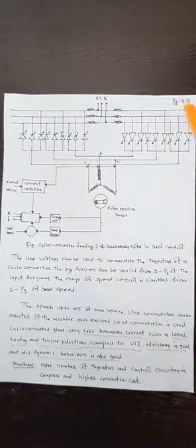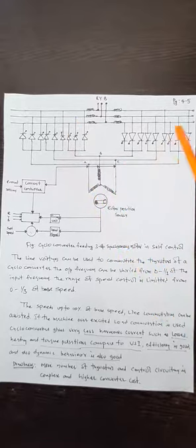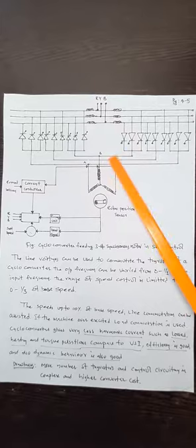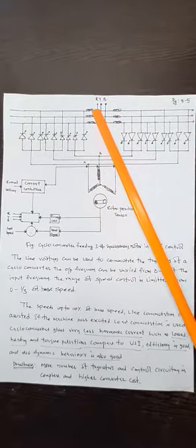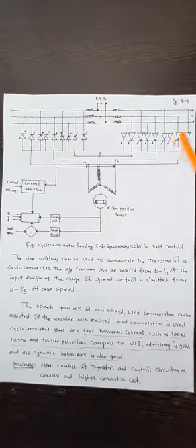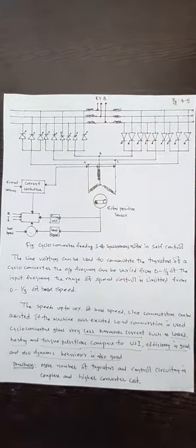With the help of the positive and negative sets, you make one connection like that. One positive, one negative, another connection. One positive and one negative, another connection. Like this, ABC, ABC phases. Yes, this is the stator phases, and this is the rotor pole phases. All the switches are control switches, all are thyristors. One is a positive group, another one is a negative group per each phase. So totally 18 thyristors.